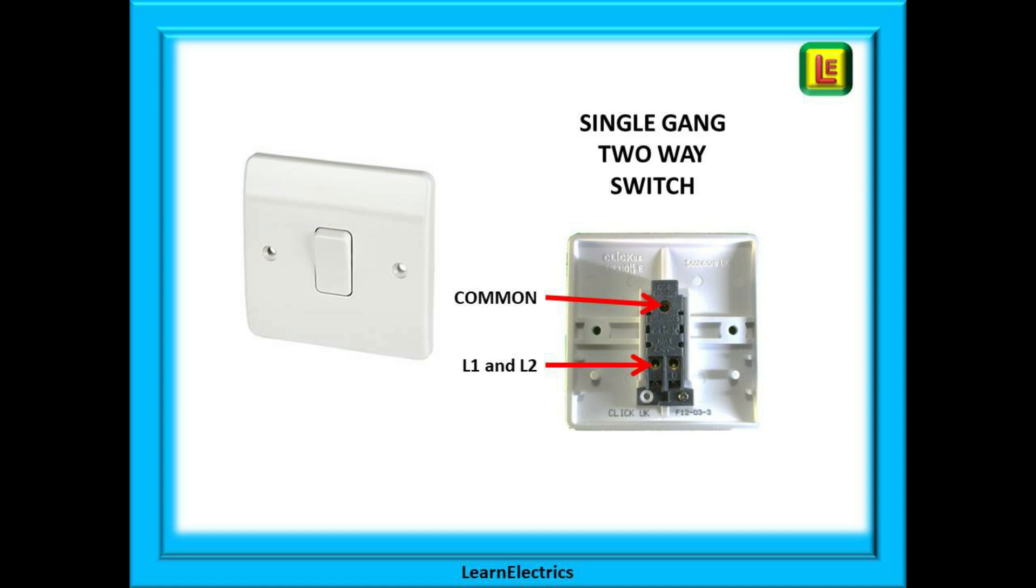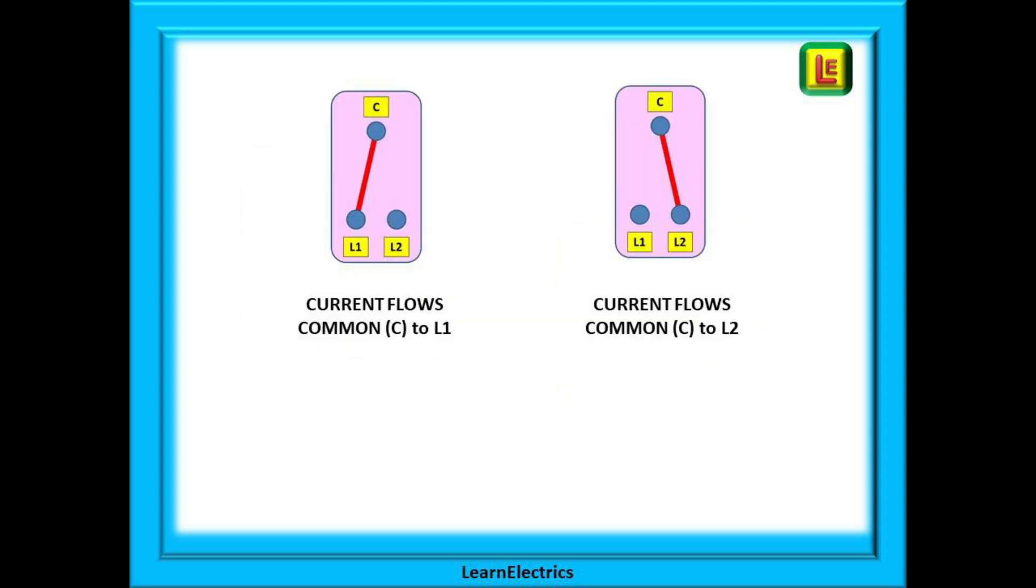Very briefly, we will be demonstrating this with single gang two-way switches. The lettering in your switch may be different as every manufacturer marks them differently, but it should be easy to relate to our switch. In our examples we have marked common as C and the two switch terminals as L1 and L2. All switches will allow current to flow from the common terminal to L1, and operating the switch will allow current to flow from the common again but this time to L2.